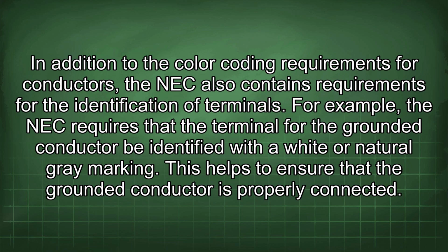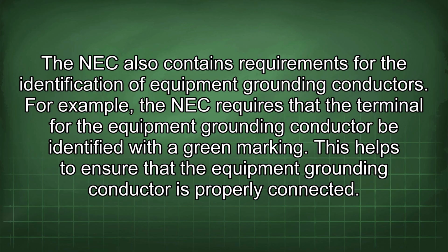In addition to the color coding requirements for conductors, the NEC also contains requirements for the identification of terminals. For example, the NEC requires that the terminal for the grounded conductor be identified with a white or natural gray marking. This helps to ensure that the grounded conductor is properly connected. The NEC also contains requirements for the identification of equipment grounding conductors. For example, the NEC requires that the terminal for the equipment grounding conductor be identified with a green marking. This helps to ensure that the equipment grounding conductor is properly connected.